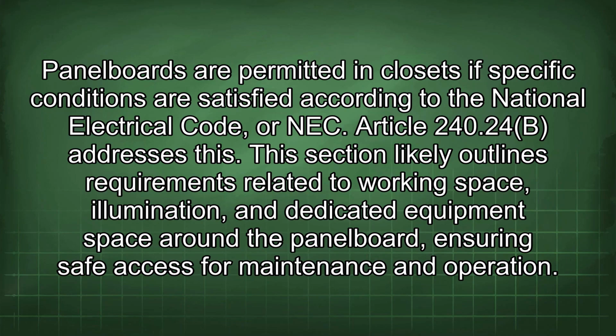Panelboards are permitted in closets if specific conditions are satisfied according to the National Electrical Code, or NEC. Article 240.24(b) addresses this. This section likely outlines requirements related to working space, illumination, and dedicated equipment space around the panelboard, ensuring safe access for maintenance and operation.